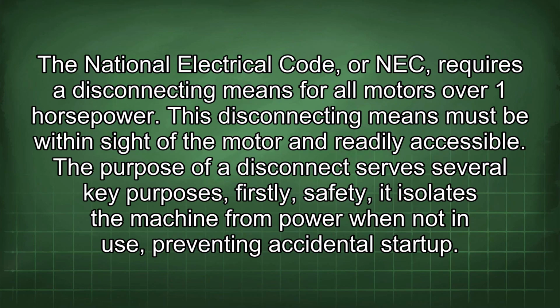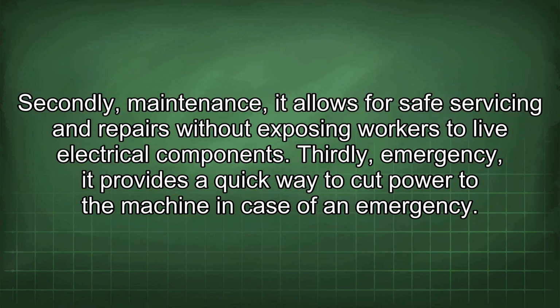The National Electrical Code, or NEC, requires a disconnecting means for all motors over 1 horsepower. This disconnecting means must be within sight of the motor and readily accessible. A disconnect serves several key purposes. Firstly, safety. It isolates the machine from power when not in use, preventing accidental startup. Secondly, maintenance. It allows for safe servicing and repairs without exposing workers to live electrical components. Thirdly, emergency. It provides a quick way to cut power to the machine in case of an emergency.